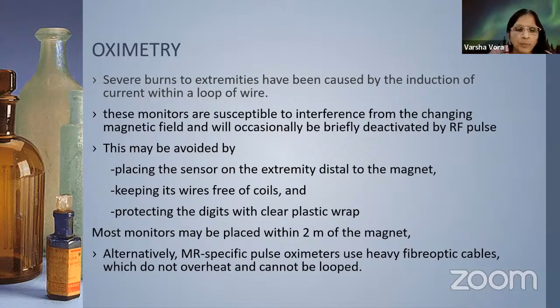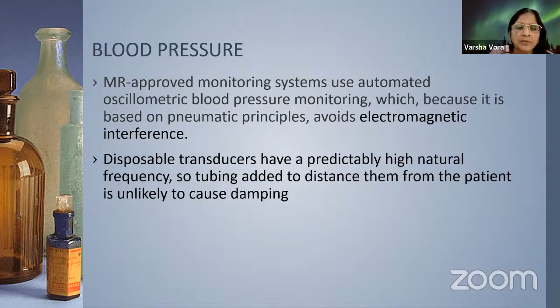Most monitors may be placed within 2 meters of the magnet. Alternatively, MR-specific pulse oximeters use heavy fiber optic cables which do not overheat and cannot be looped. Blood pressure: MR-approved monitoring systems use automated oscillometric blood pressure monitoring which, because it is based on a pneumatic principle, avoids electromagnetic interference.